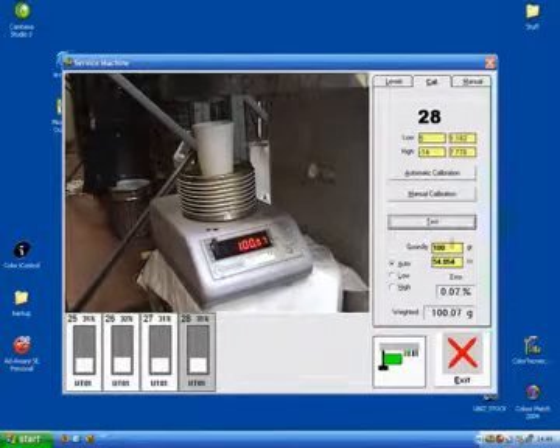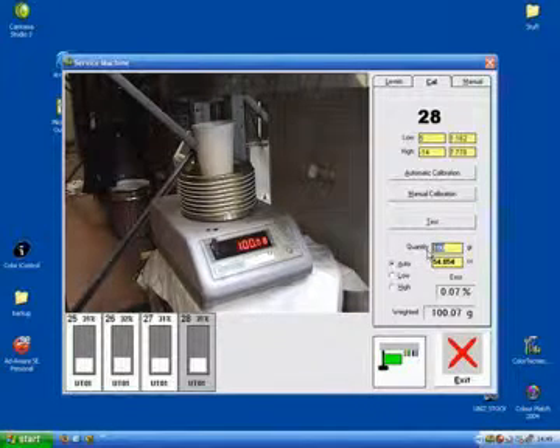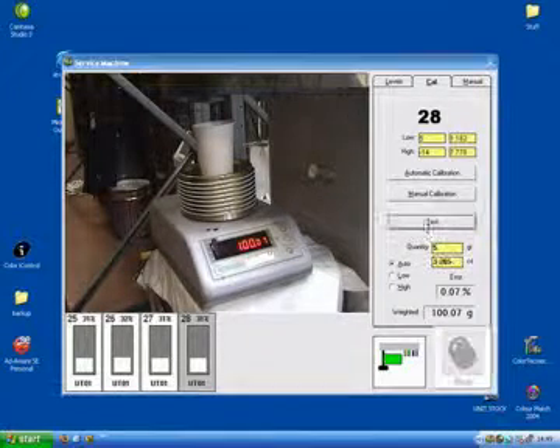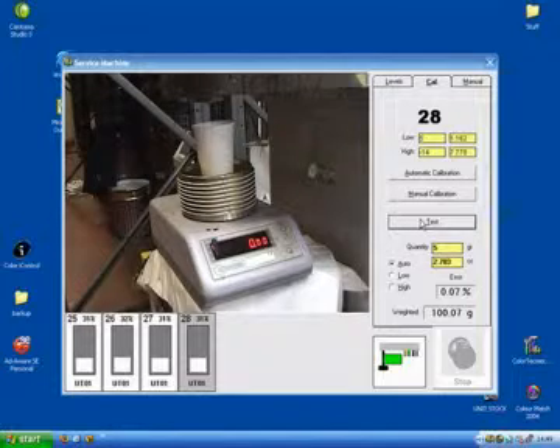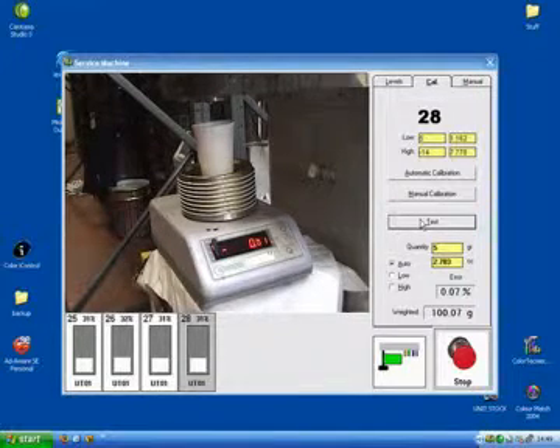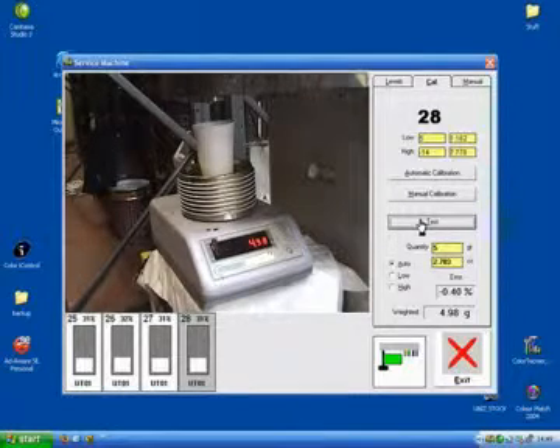Now if we put 5 grams into the test box and click the test button, it will dispense 5 grams of colorant at low speed. Usually, we tolerate anything less than 1% error. However, if the error is greater than 1%, we recommend a recalibration on this tank.